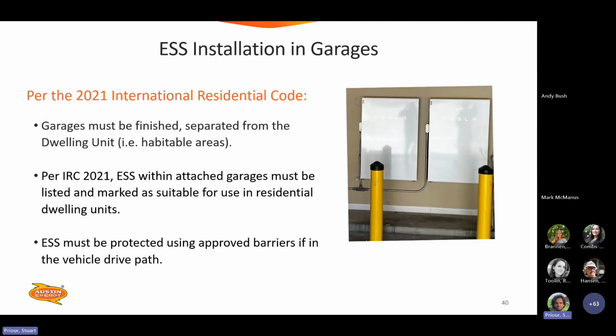Installation of ESS or batteries in garages. So we use the 2021 International Residential Code. The garage must be finished and separated from the dwelling unit, i.e. the habitable area. So per IRC 2021, ESS within attached garages must be listed and marked as suitable for use in dwelling units. They've also got to be protected using approved barriers if the vehicle is in the drive path. So you don't need one every time in a garage, but often you do. So that's something that you might want to request a pre-construction meeting for.